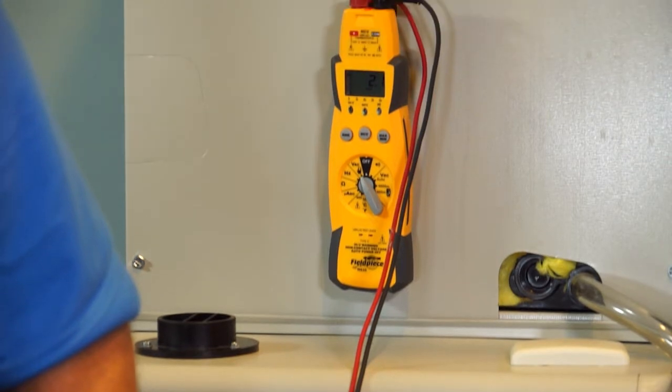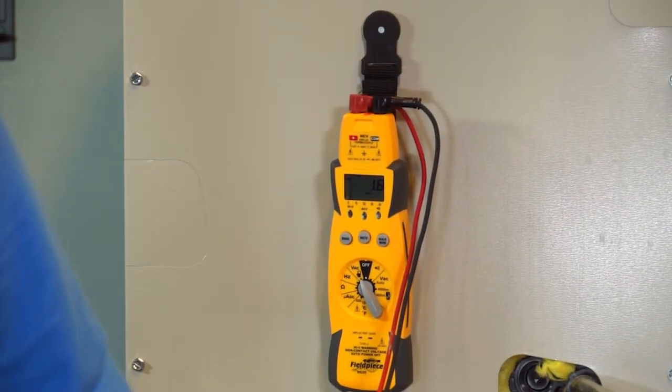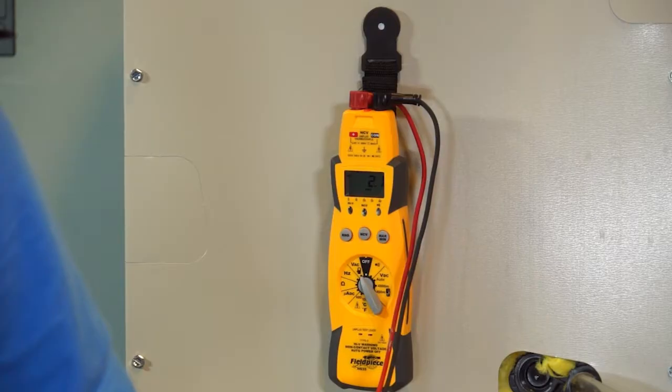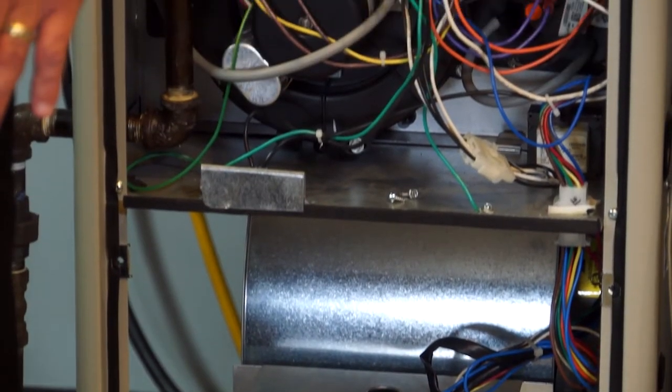So I've got a G7 two-stage furnace here with way too high resistance in the limit circuit and I wanted you to see it for yourself and what it can do. The other thing I want to point out in this video is this is just one example. High resistance in a limit circuit, high resistance in a pressure switch, it really doesn't matter where that high resistance is at. It can make circuit boards do weird things and you think that maybe you got a bad circuit board when you don't. So it's very important that you're taking the time as a technician to test these circuits.